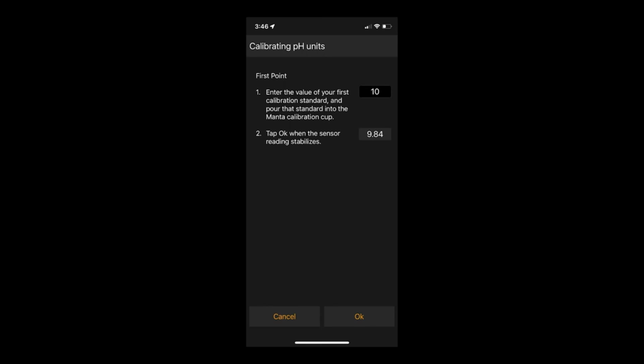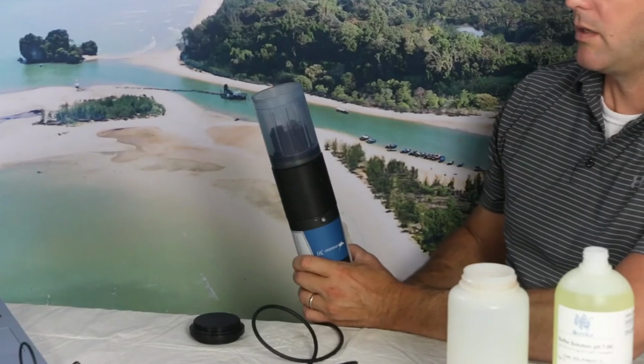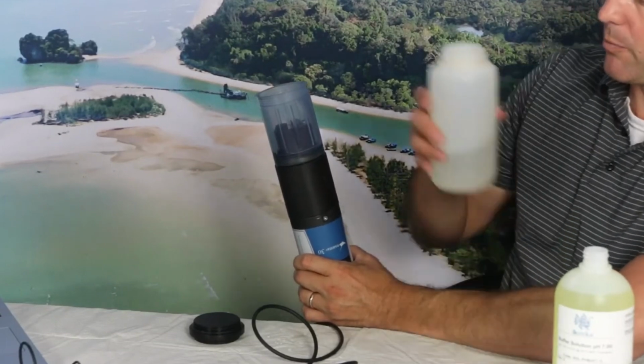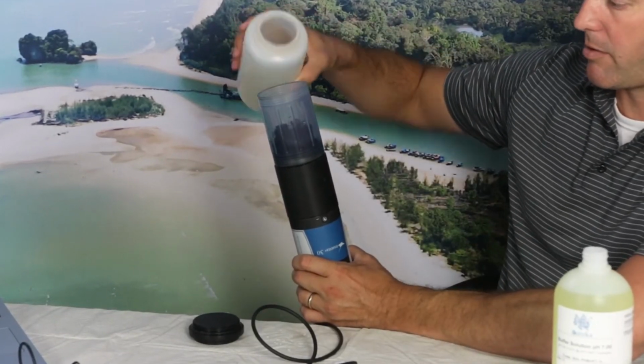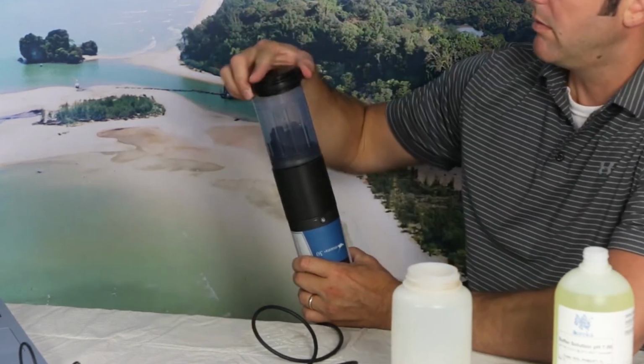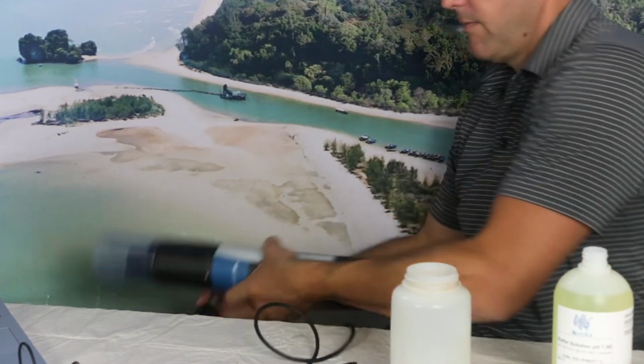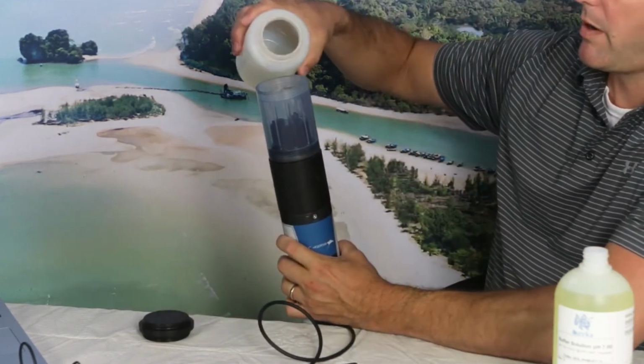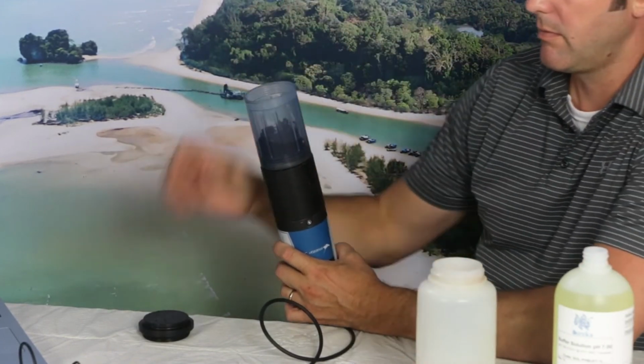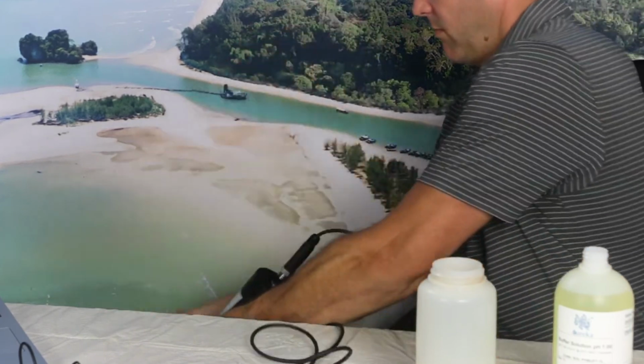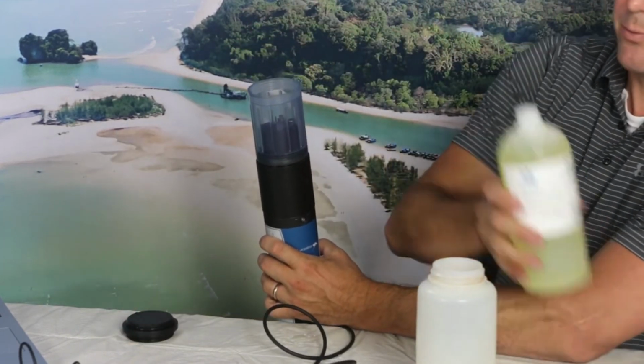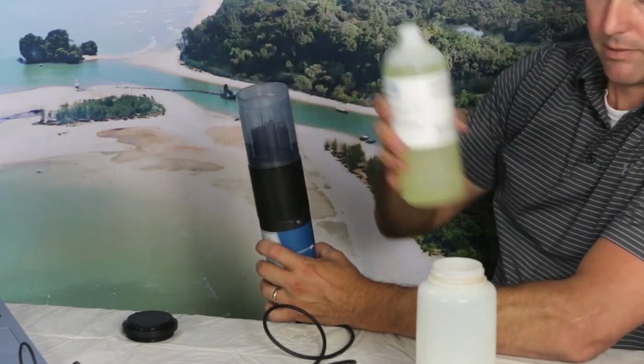With your calibration solution in the cup, type the value of that calibration solution in the text field on your screen. Wait for that reading to stabilize, and then tap OK. To calibrate your second point, we're going to do our rinsing process once again with our DI or RO water. Second rinse with water. Then 2 rinses with our 7 buffer.